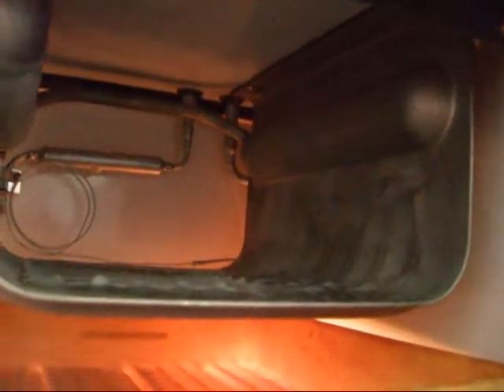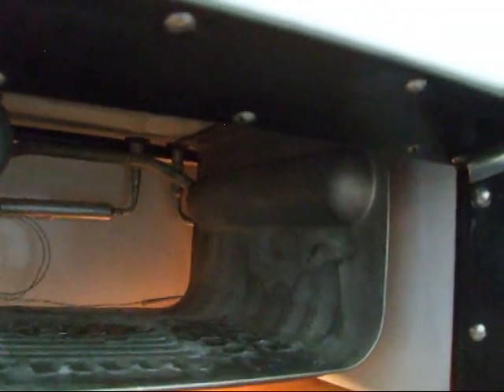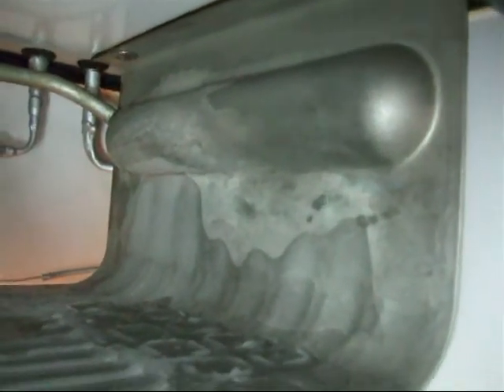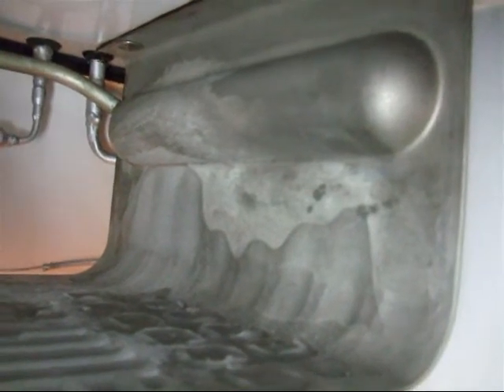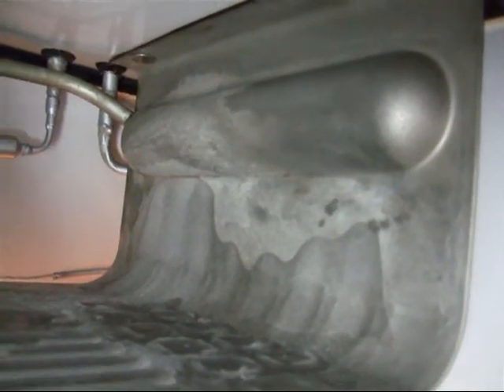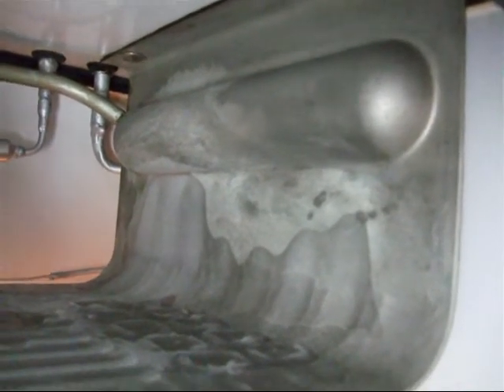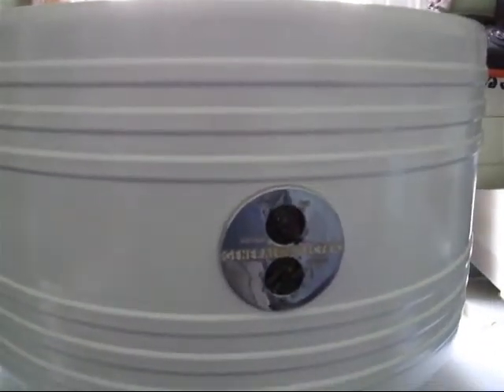I'll show you just in here — you can see that the frost line has fallen well below the right header tank. It should be at least a quarter of the way up. So that's one indication. And also, when the machine starts up, the rattling is rather pronounced.